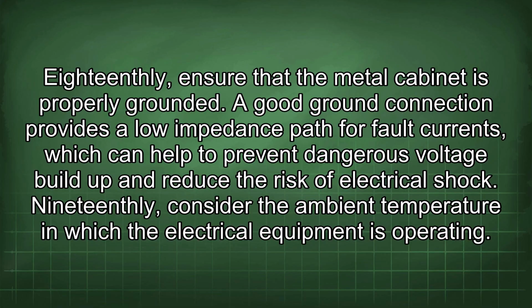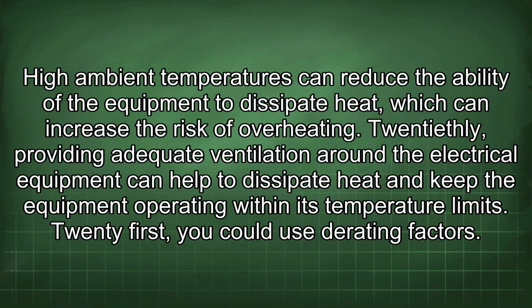19th, consider the ambient temperature in which the electrical equipment is operating. High ambient temperatures can reduce the ability of the equipment to dissipate heat, which can increase the risk of overheating. 20th, providing adequate ventilation around the electrical equipment can help to dissipate heat and keep the equipment operating within its temperature limits. 21st, you could use derating factors.